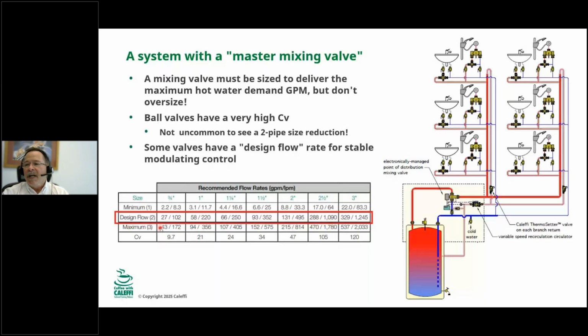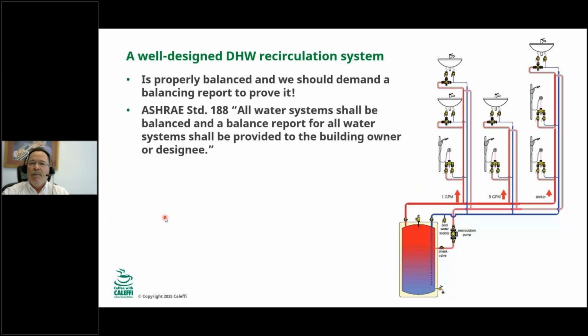Balancing. Let's talk about balancing. This is the big one. We really need to get balancing contractors to produce a balancing report. I hear almost every day, oh yeah, right, good, you want it, but it just doesn't happen. They never see balancing reports. It's too bad, but it's near the end of the job. They're one of the last contractors on the job, and if it's behind schedule and they're over budget, sometimes the report doesn't get done. But there's a lot of references here that tell us if at all possible, we need to have that done. ASHRAE standard 188, for example.